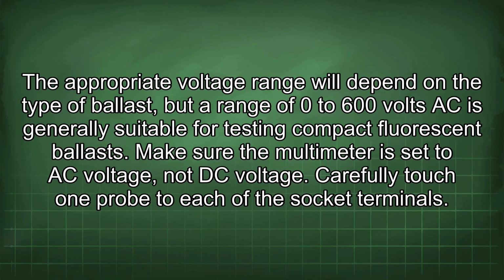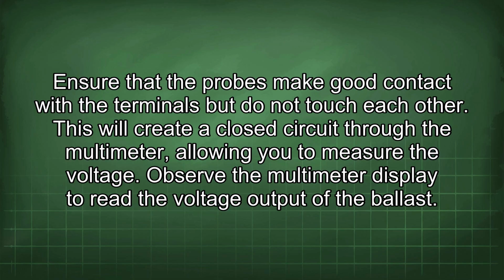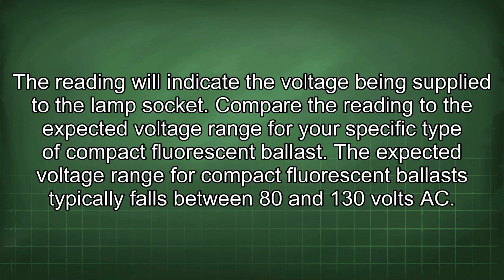Carefully touch one probe to each of the socket terminals. Ensure that the probes make good contact with the terminals but do not touch each other. This will create a closed circuit through the multimeter, allowing you to measure the voltage. Observe the multimeter display to read the voltage output of the ballast. The reading will indicate the voltage being supplied to the lamp socket.